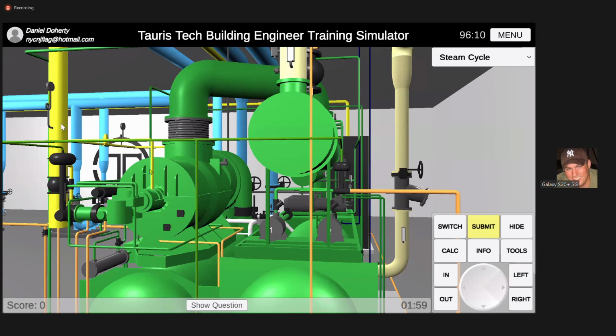Look, you got steam coming in, right? It goes to the governor, goes to your trip valve, comes out the nozzles, hits the turbine blades. As the steam hits the turbine blade, it gives up its energy, and when it gives up its energy, the steam starts to condensate. It starts to condense. So the rest of the steam exhaust goes through the exhaust, but the condensate that's left in the casing comes out of your drains right here. You see these two drains?